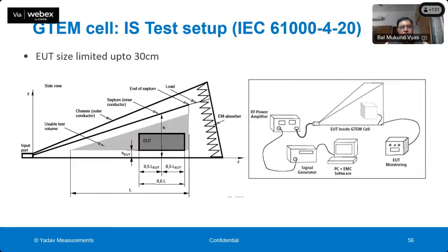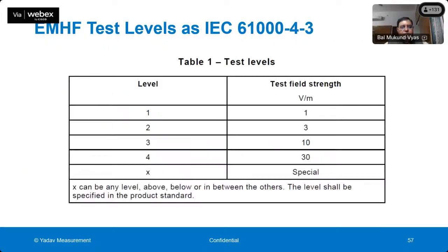This test can also be done in another kind of device, which is called a GTEM cell, which is relatively cheaper, but there is a size limitation: a maximum of 30 centimeter meters can be tested in these kinds of chambers, GTEM cells. Various kinds of field strengths are specified, as you see in IEC 61000-4-3.